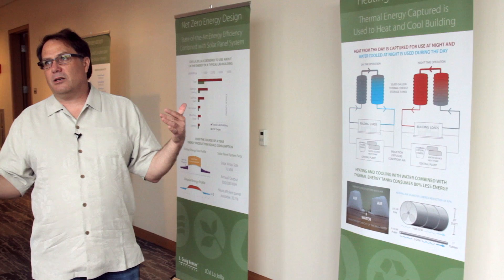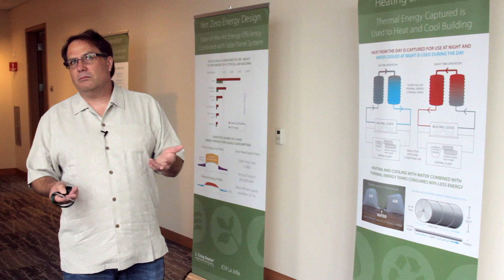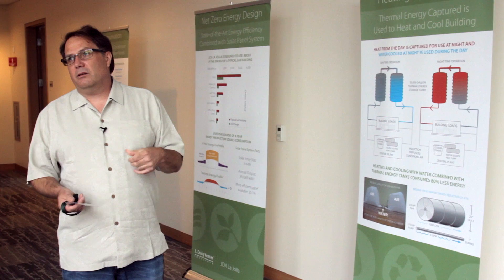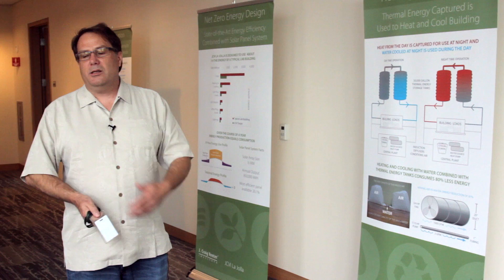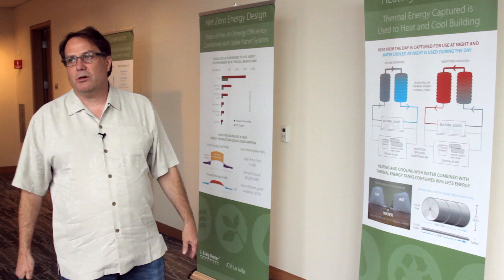As a design firm we also size our duct at a lower flow rate. Industry standard is 0.08 to 0.1 inches per 100 feet of static pressure; we design at 0.05. That lower static pressure drop reduces energy tremendously because it follows a square or cube root rule, so your horsepower requirement falls significantly.